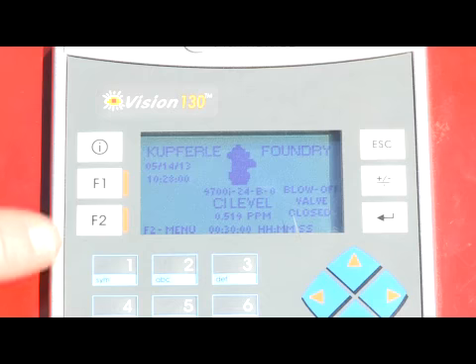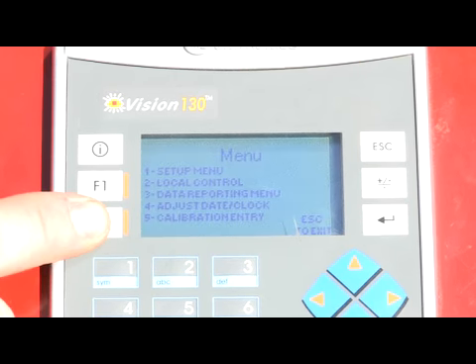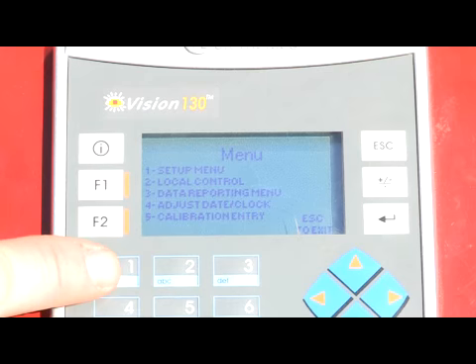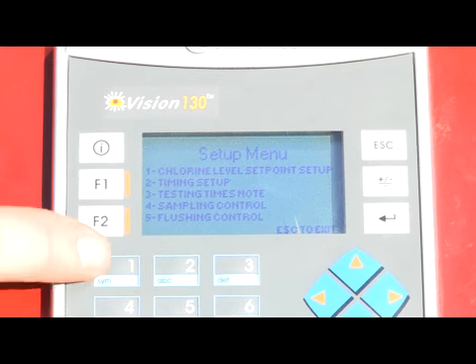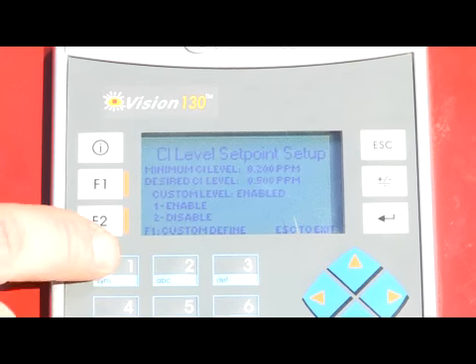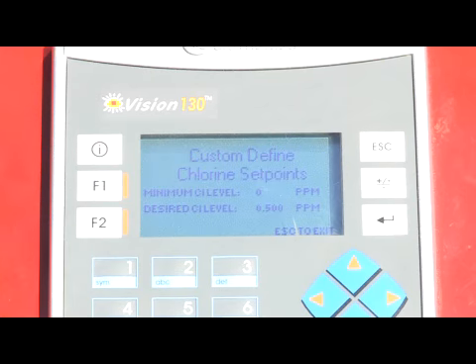Unlike regular automatic flushing systems that operate on a daytime duration schedule, intelligent flushing revolves around sampling. Using the PLC, the user would program the PLC's minimum residual level. Additionally, they would program the PLC's desired residual level.